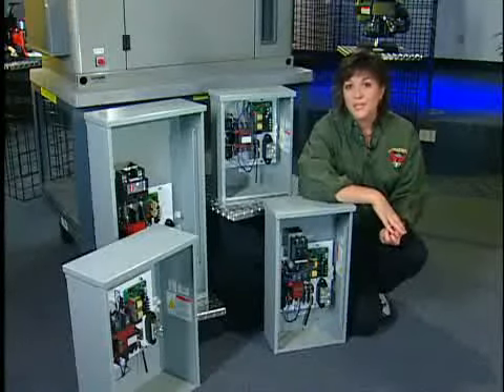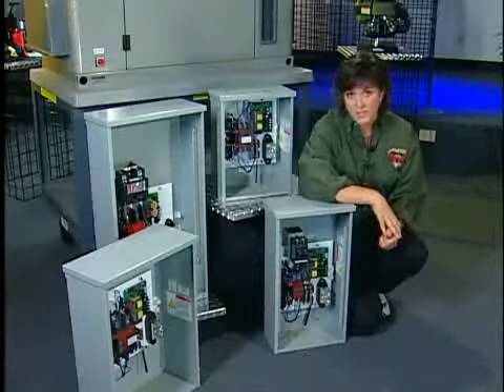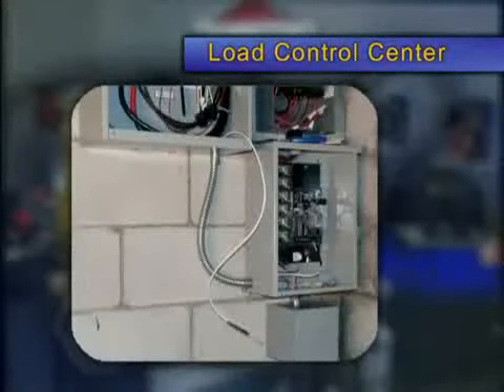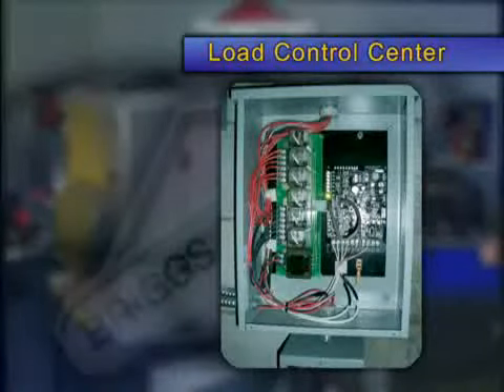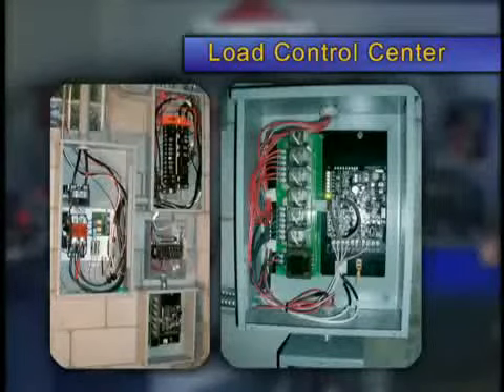The last item pertaining to transfer switches is the load control center. This works in conjunction with the ACCM. Once the automatic transfer switch transfers to generator power, the load control center will shed loads in a predetermined order of priority until enough power is available to start the air conditioner. Once the air conditioner is running, the load control center will return power to the loads that were shed until it reaches about 80% of maximum load. Two air conditioners can be controlled. This feature allows the use of a smaller kilowatt generator and reduces the overall installation costs.